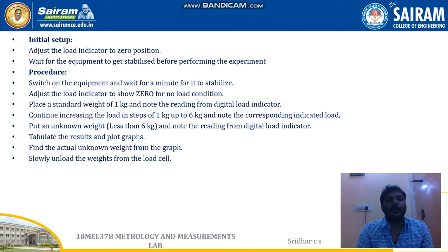Now we'll see the procedure to conduct this load cell experiment. The first thing is you must switch on the equipment and wait for a minute for it to stabilize. Next, adjust the load indicator to show 0 for the no load condition. So we need to adjust the indicator to the zero position for the no load condition.